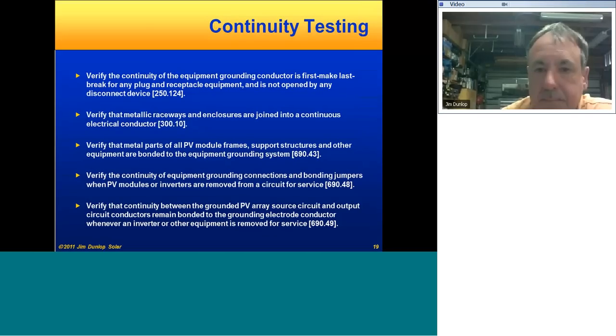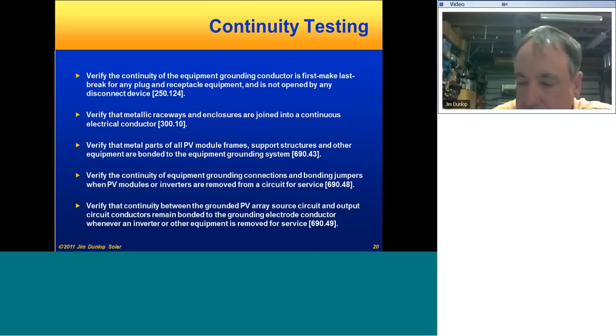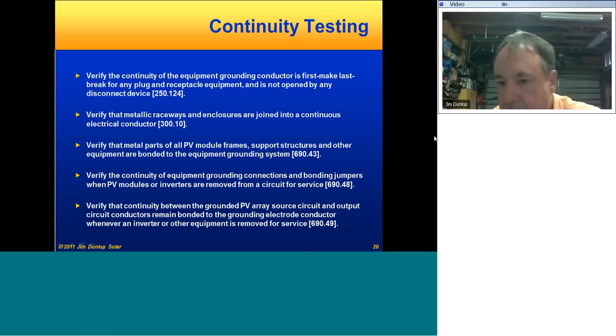Any kind of plug and receptacle connection can be verified through continuity testing, and it helps track down crossed wires or mixed-up source circuits, things like that. Obviously, verifying all the equipment grounding, again, that's in Article 690.43. It covers the equipment grounding connections and bonding jumpers between modules and inverters if you remove them for service, and maintaining continuity of those connections across the entire support structure. We're using a lot of different equipment and special equipment bonding washers to make those connections.